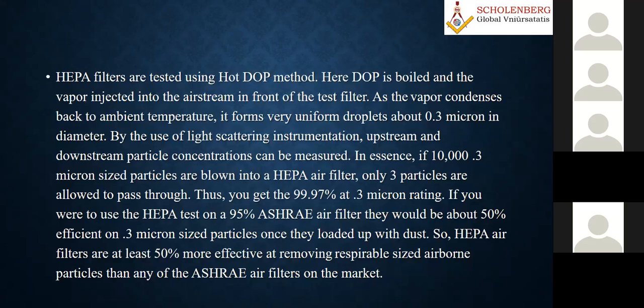So as I told you, HEPA filters are tested using the hot DOP method. Here DOP is boiled, and the vapor injected into the air stream. As the vapor condenses back to ambient temperature, it forms very uniform droplets, measured by use of light scattering instrumentation. The physics of that light scattering instrumentation I'm skipping; most of that I'm assuming you know.